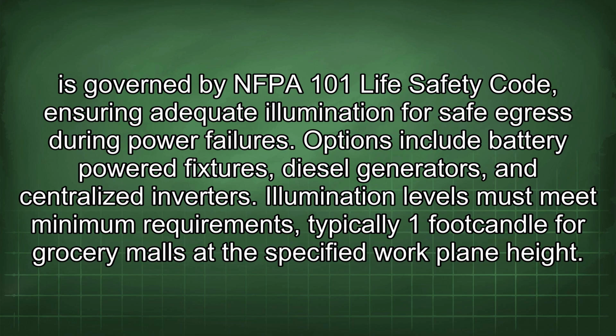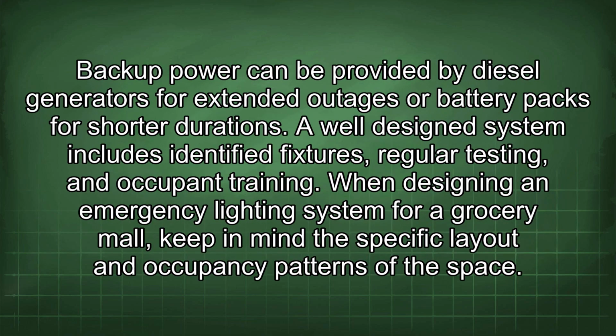Options include battery-powered fixtures, diesel generators, and centralized inverters. Illumination levels must meet minimum requirements, typically 1 foot-candle for grocery malls at the specified work plane height. Backup power can be provided by diesel generators for extended outages or battery packs for shorter durations. A well-designed system includes identified fixtures, regular testing, and occupant training.